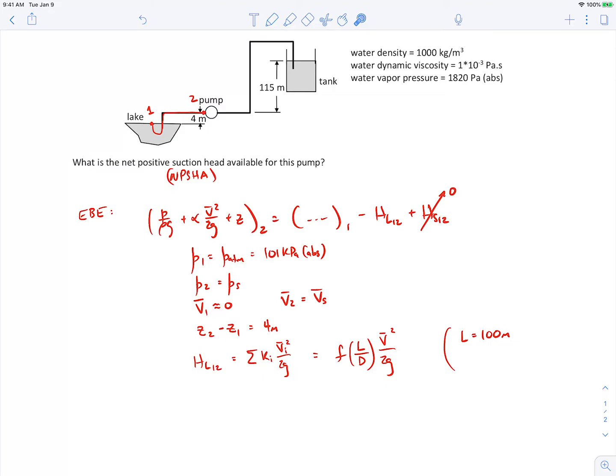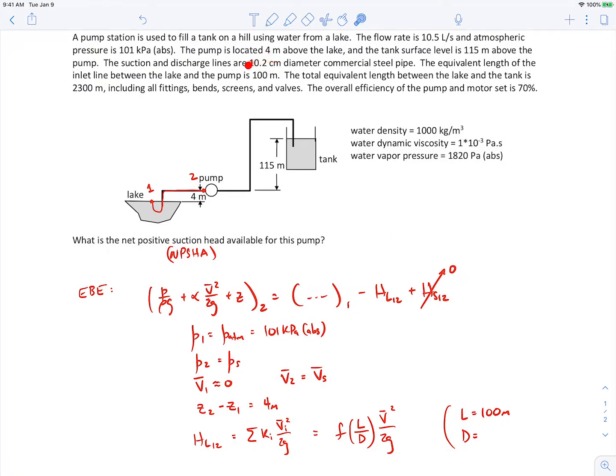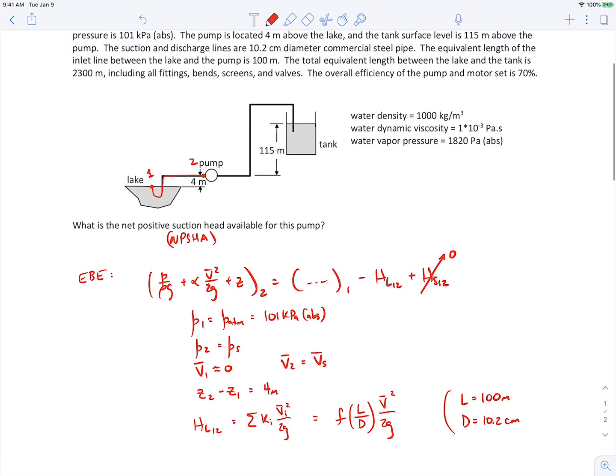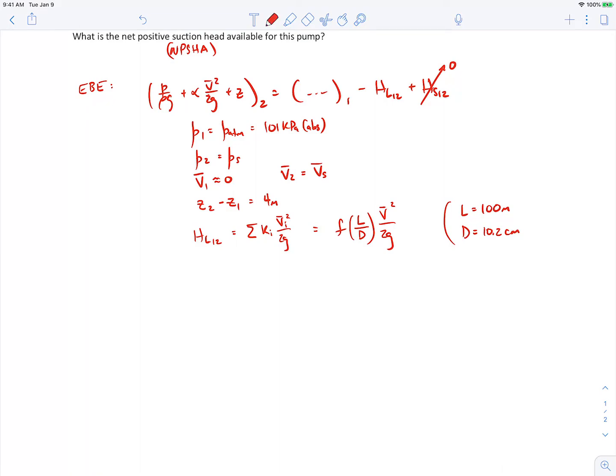We're only worried about the upstream part of the pipe system, upstream of the pump. The suction line diameter is 10.2 centimeters, and we're dealing with commercial steel pipe. We can look up the roughness for commercial steel pipe from a table — it comes out to 0.045 × 10⁻³ meters. We calculate the relative roughness, which comes out to 0.00044. We also need the Reynolds number along with the roughness to find the friction factor.